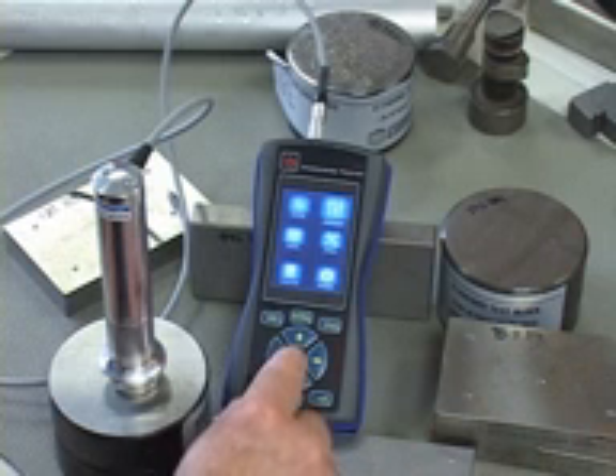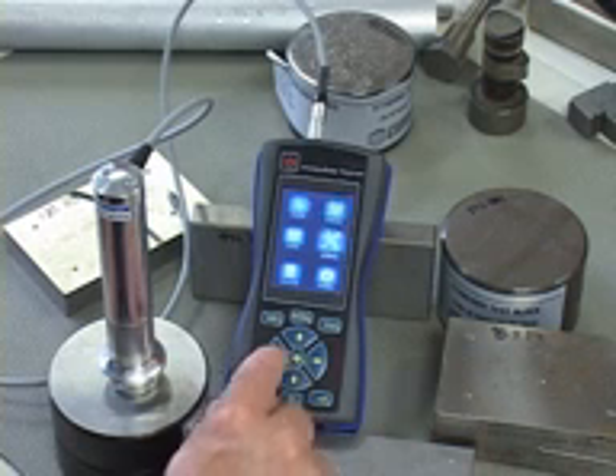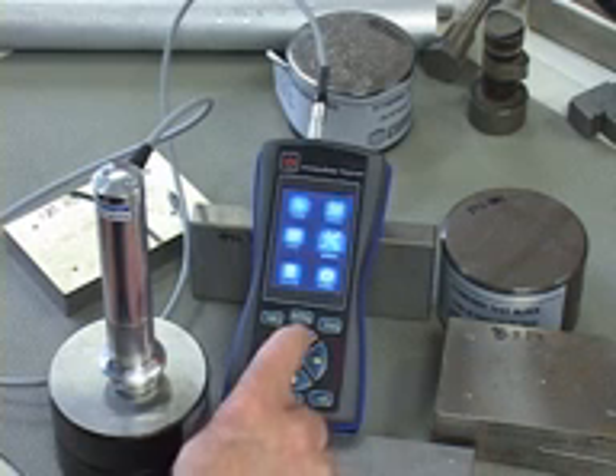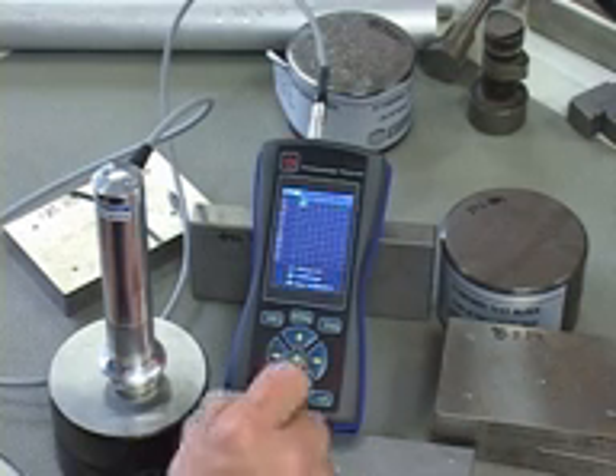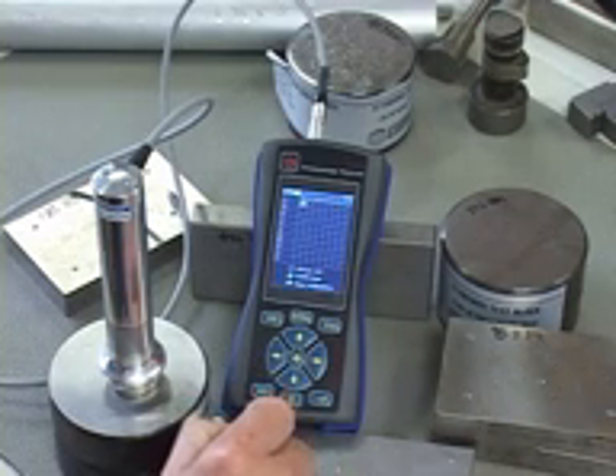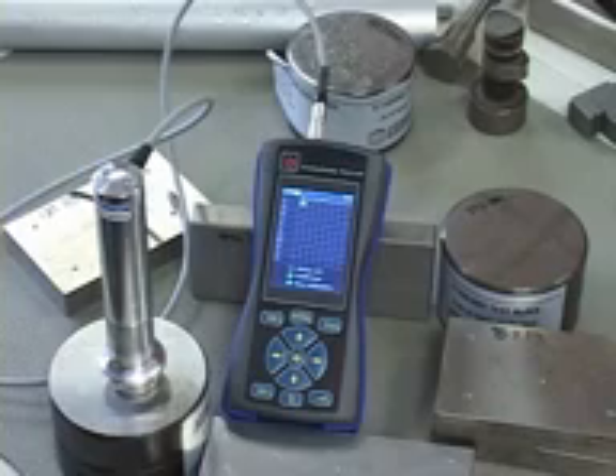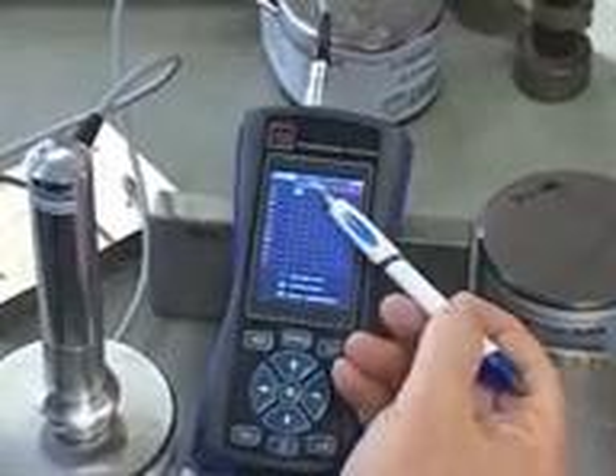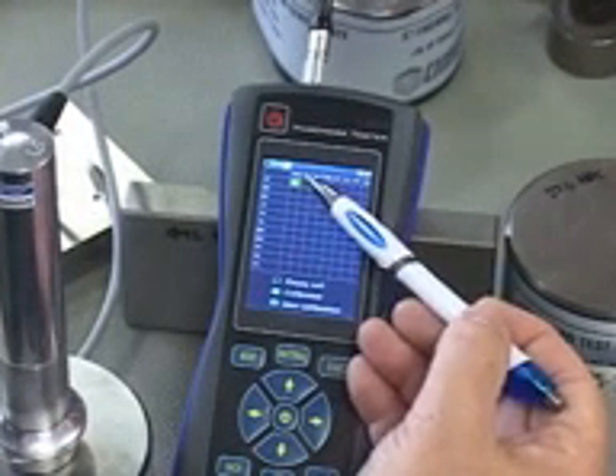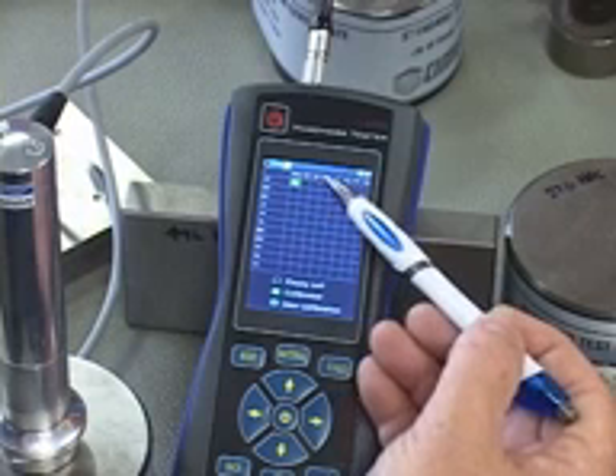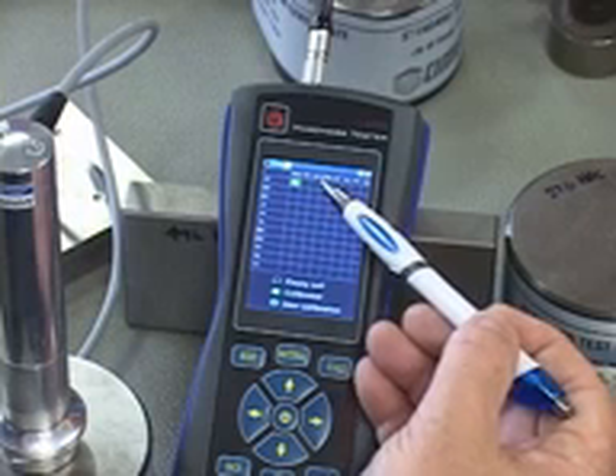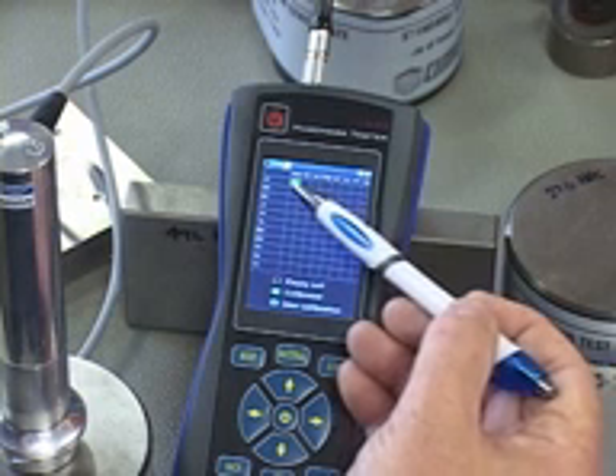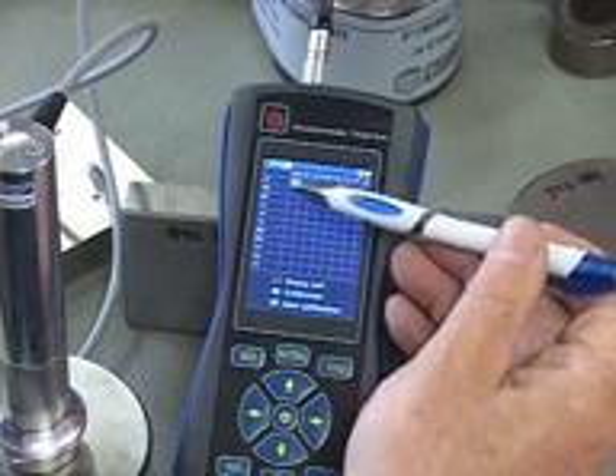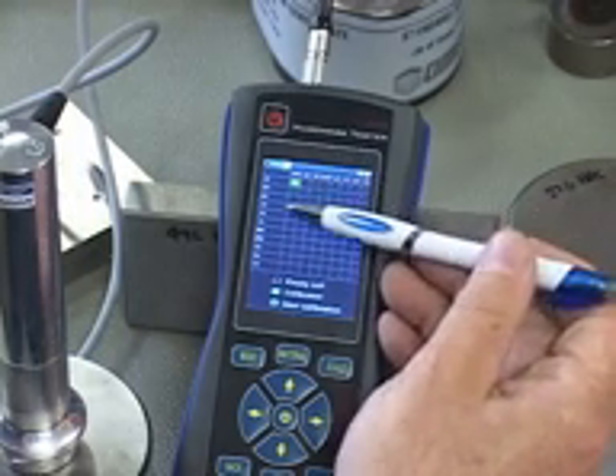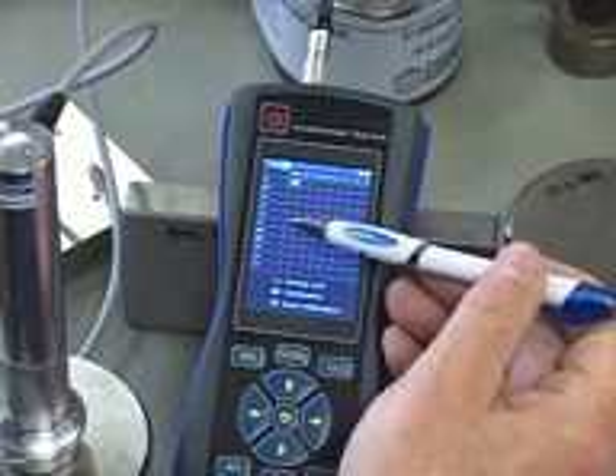So I'm going to hit the middle mouse button to go into calibration, because you can see here if I move around it changes the size of the icon larger. So here we are in calibration, and right now it's showing that we have one calibration. It is for HRC. Next to it would be HB Brinell, and then Vickers. HRB is only used when we've got the D-type test probe attached. And then down here are different material types. Then we have alloy steel, stainless steel, cast iron, aluminum, and so on.